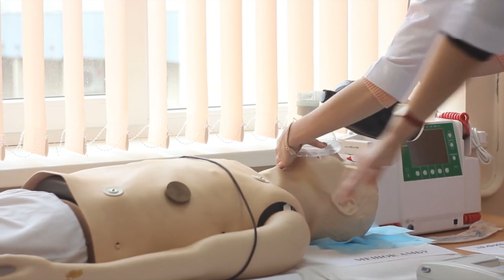To make sure that no defects or slow deterioration of devices are missed, the hospital must have procedures for planning and registering maintenance, for getting and using the correct spare parts, and for measuring and validating quality and performance of their devices. Sometimes faults or malfunctions cannot be prevented because it just happened suddenly or due to the device being dropped or maltreated. Therefore, it is important to have procedures for reporting and keeping records of any adverse events, and there must be a plan for what to do when it is discovered that a faulty device has been used on one or more patients before the fault was discovered.